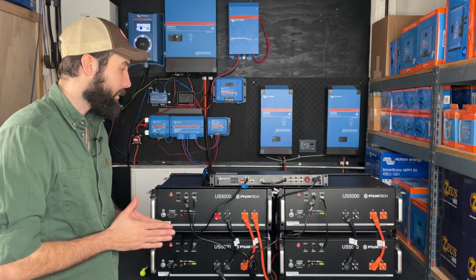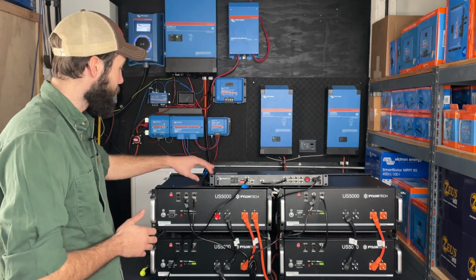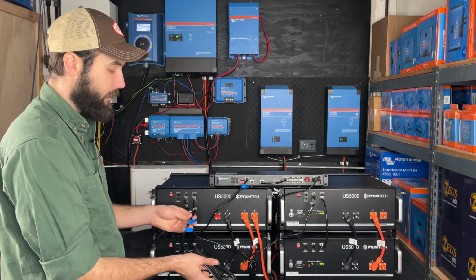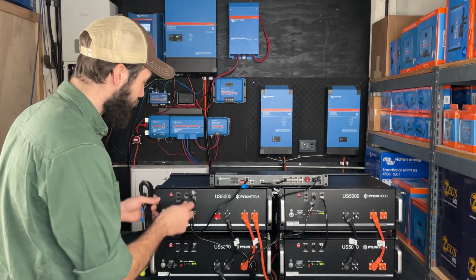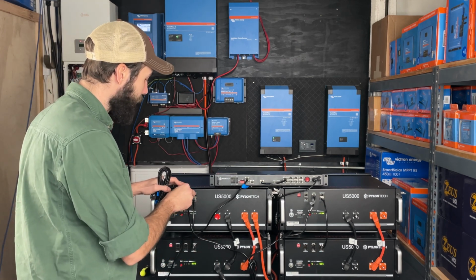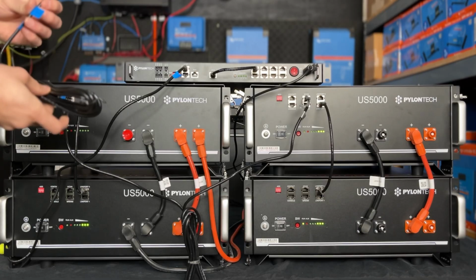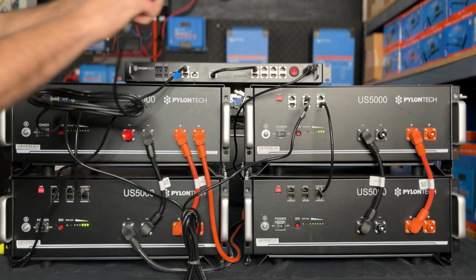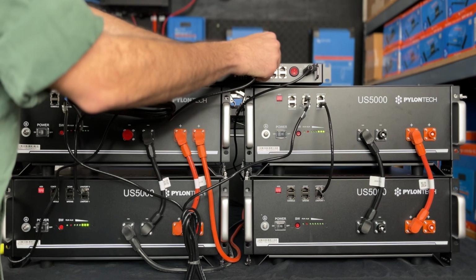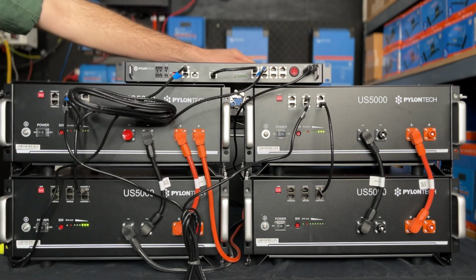Now that we have that connected, we take our battery-to-inverter communication cable. We plug the battery side into the CAN of the master battery, and the inverter side into port number 1 on our combiner hub.